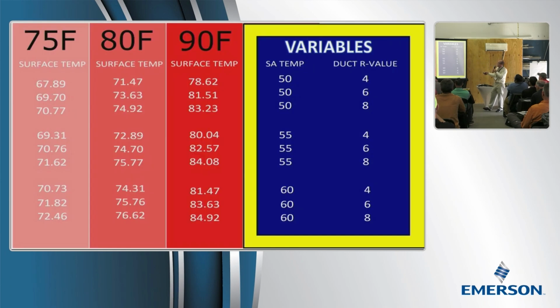What I'm going to do here is take these temperatures and look at them under a couple of different circumstances: where the air around the duct is 75 degrees, 80 degrees, or 90 degrees. Then we're going to throw some variables at it—is the supply air temperature 50? Is it 55? Is it 60? And we're going to take a look and see what that does to us.